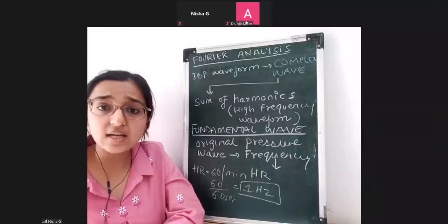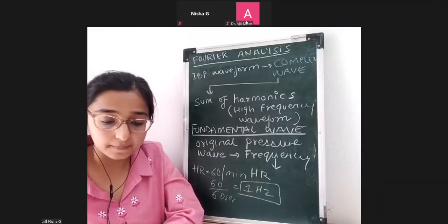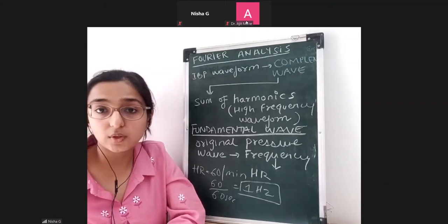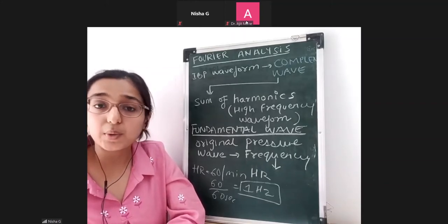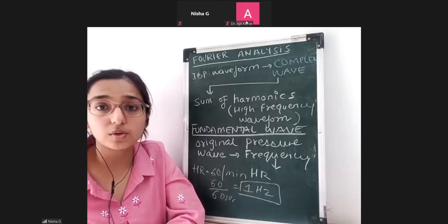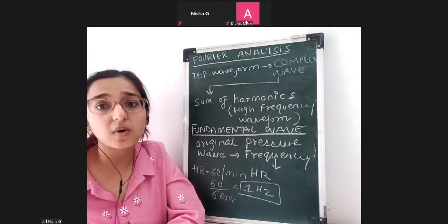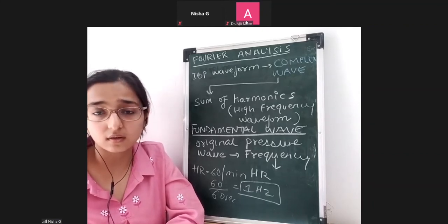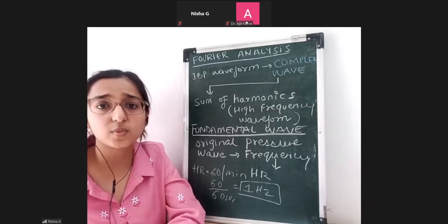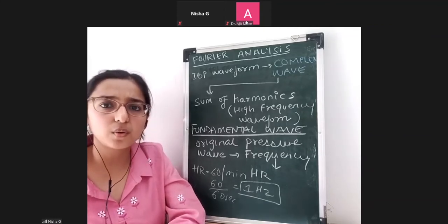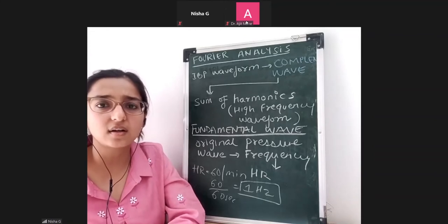What is the fast flush test? Okay, so I told you fast flush will tell us what you have set up, the whole system. You're telling me, ma'am, I want to know what's the dynamic response of the system that I've set up. I really want to know what's the natural frequency. I want to know how much is the damping. I can't really rely on what's given in the package which has come, because of any reason. You just want to know what's the actual current condition, right?